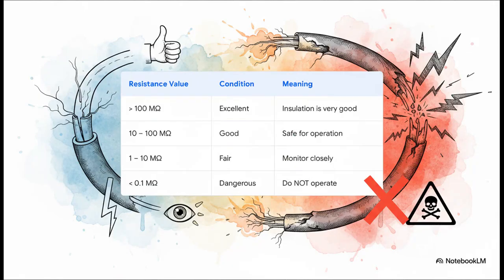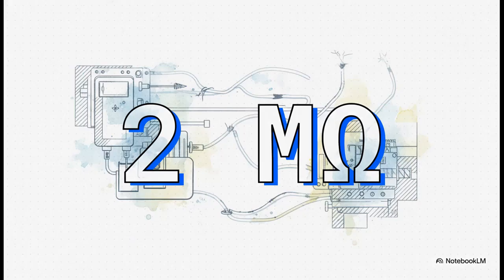This is where we translate those raw numbers into simple, clear instructions. Anything over 100 megaohms, that's excellent. You're in great shape. Between 10 and 100, still good. You're safe to operate. But once you dip below 10, you really need to start paying close attention. And if you get a reading below 0.1 megaohms, that piece of equipment is dangerous. Do not operate it.